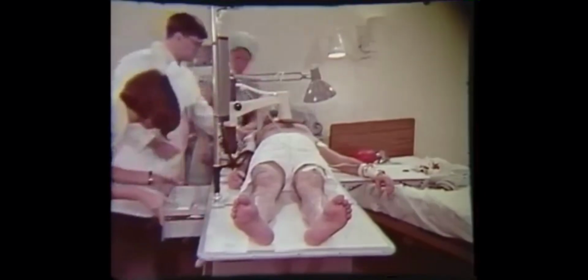Check ventilator and intravenous connections for security. Unplug the line cord. Store the wall oxygen hose after turning on one oxygen tank. MAX will now function independently. A distinct change in cardiac compressor sound warns that oxygen pressure will fail in 10 seconds. Turn on the second E-tank immediately to maintain oxygen pressure while replacing the first tank. Never operate from both E-tanks simultaneously, and move the patient only while operating from one tank with the second unopened tank in reserve.